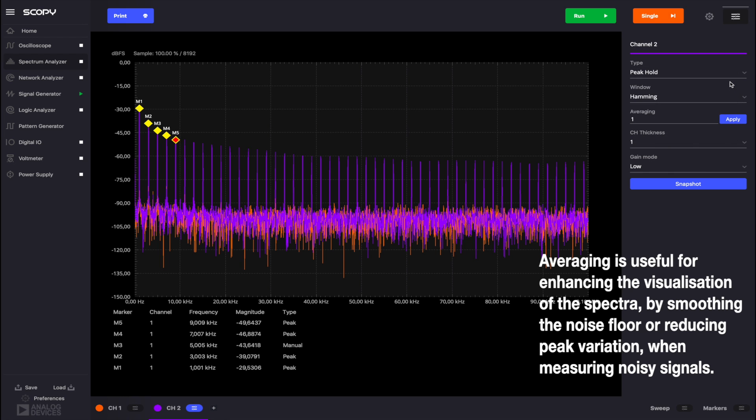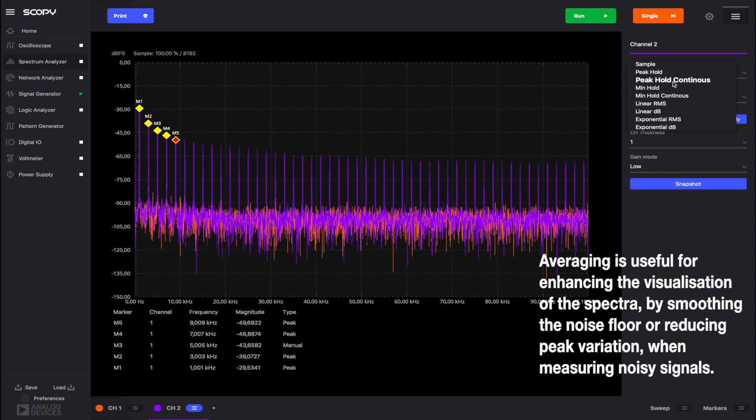For any of the options except sample, you can set the desired number for averaging. Let's set the type to peak hold continuous and an averaging of 100. Run the instrument.